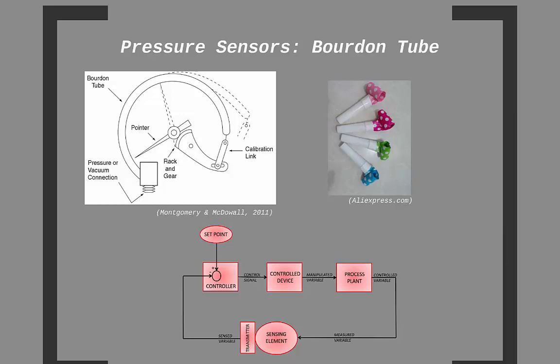There are many other pressure sensor configurations which incorporate the deflection of some device due to changes in the pressure it is exposed to, in an effort to indicate fluid pressure. There are other devices that measure the change in electrical resistance of a material when stretched. Such stretching can be performed by attaching the material to a component in the pressure gauge, which will deflect when exposed to different fluid pressures. This is very similar to the science behind some of the temperature and relative humidity sensors previously discussed.